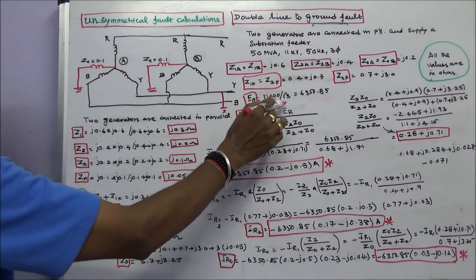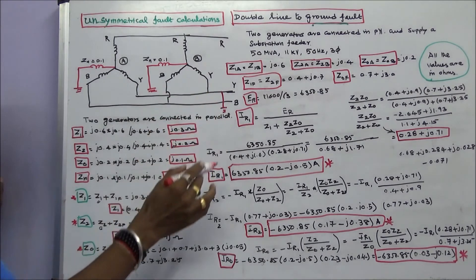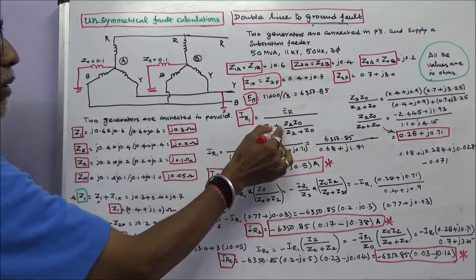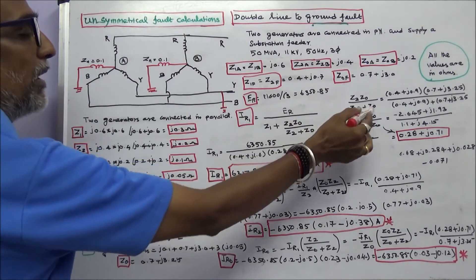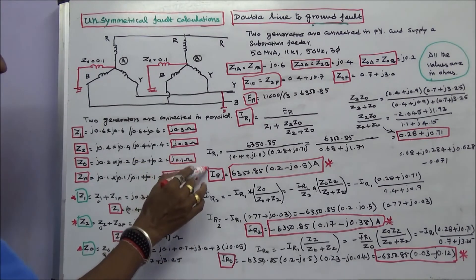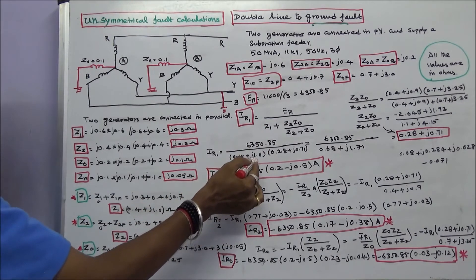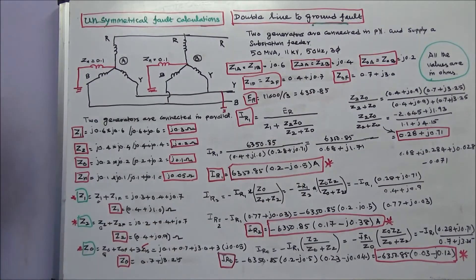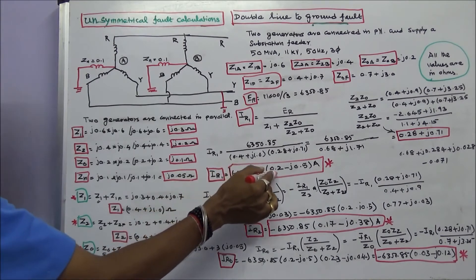Er equals 11000 divided by root 3, which equals 6350.85 volts. Now we calculate IR1, IR2, and IR0. IR1 equals ER divided by Z1 plus the parallel combination of Z2 and Z0, where Z2 times Z0 divided by Z2 plus Z0 equals 0.28 plus J0.71 ohms. Therefore IR1 equals 6350.85 times (0.2 minus J0.5).